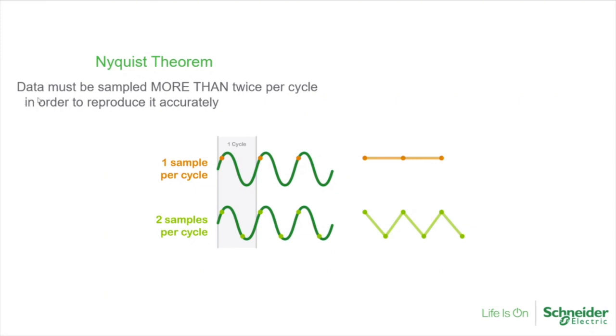And then the Nyquist theorem, also dealing with sampling, says data must be sampled more than twice per cycle in order to reproduce it accurately. The example on the screen: if we have one sample per cycle, you're going to get a straight line. If you have two samples per cycle, it looks like a triangle wave shape. But the more samples we have, the better representation of the power signal you'll get.